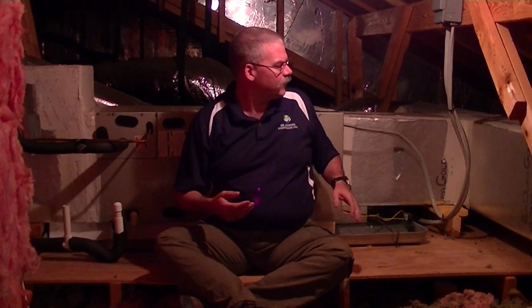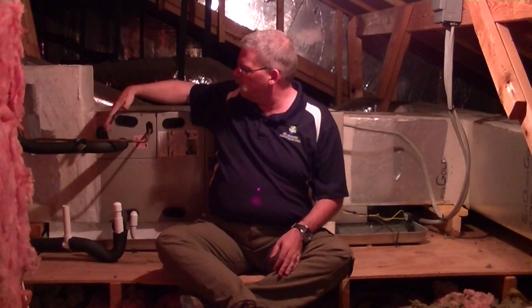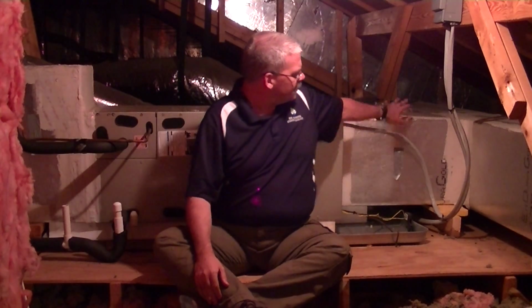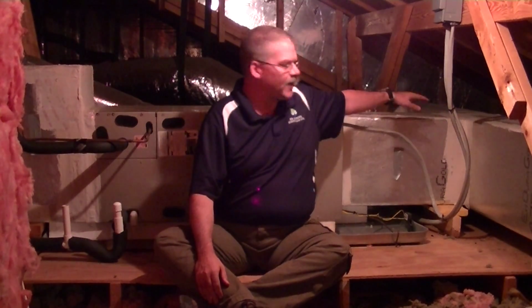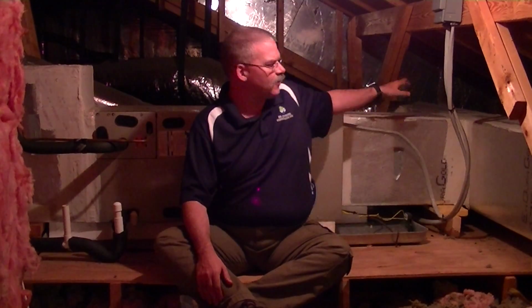So we're up here in this attic and we're looking at a heat pump air handler, which is in a split system. You've got an outdoor coil and you've got an inside coil. In this case, this is the return side, so this is connected to the return grill, with the return duct coming into the return side of the air handler at the bottom end, where we have a coil with the refrigerant lines running through it. Then there's a fan over here that's pulling the air from the house across that coil and pushing it into the supply plenum on this side, where it kind of hammerheads into this T and goes into a reducing trunk system with takeoffs.